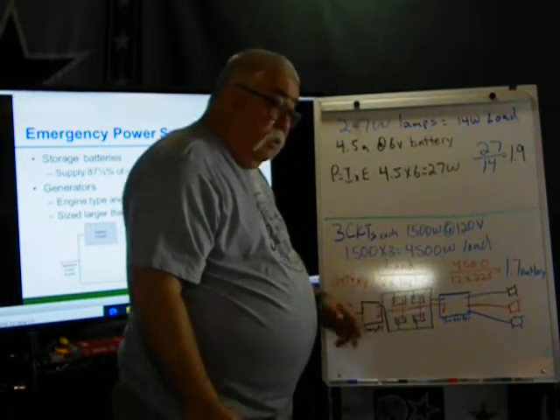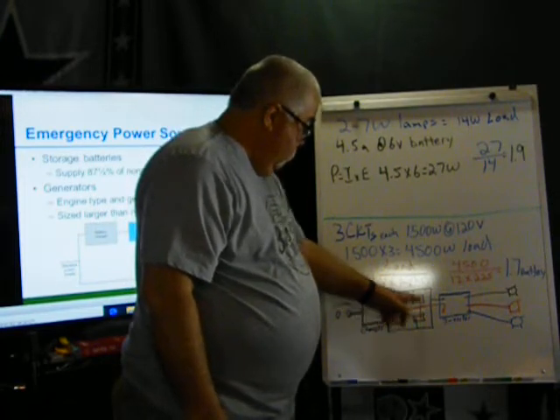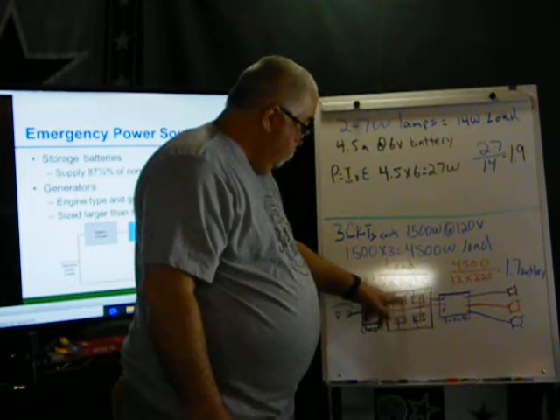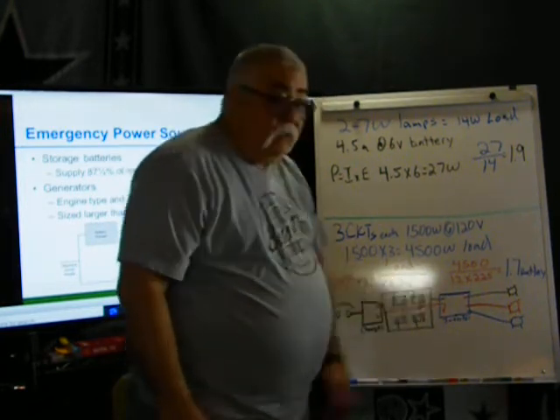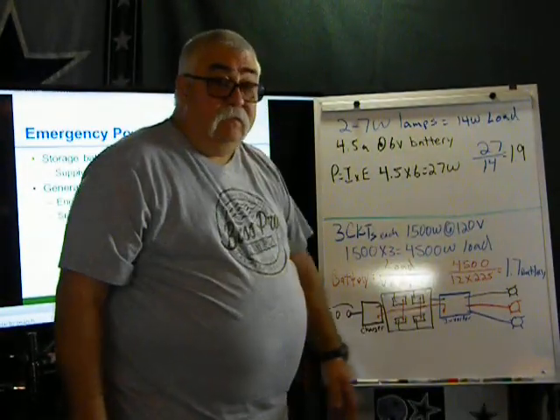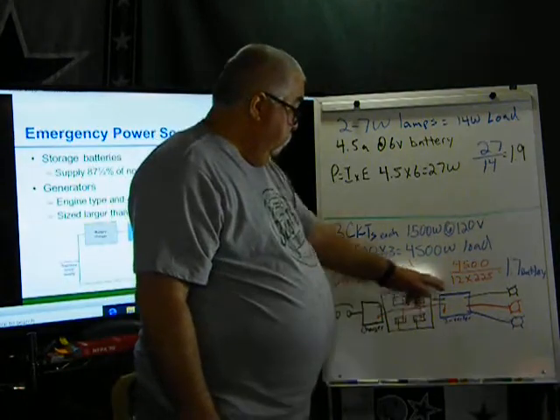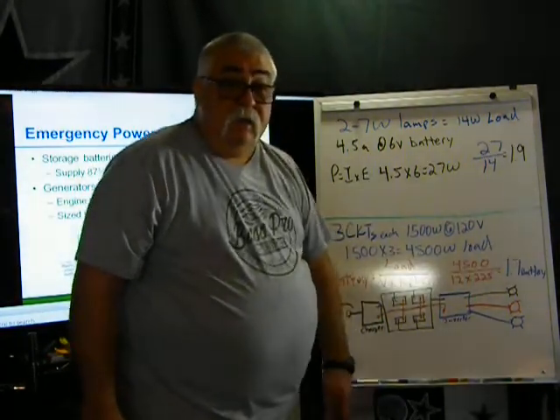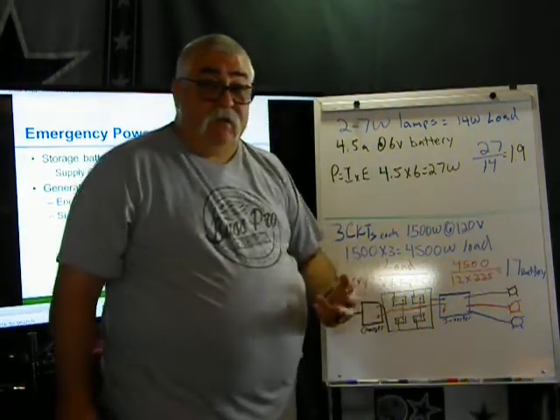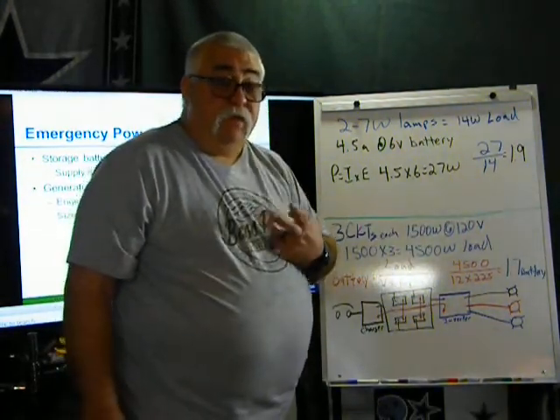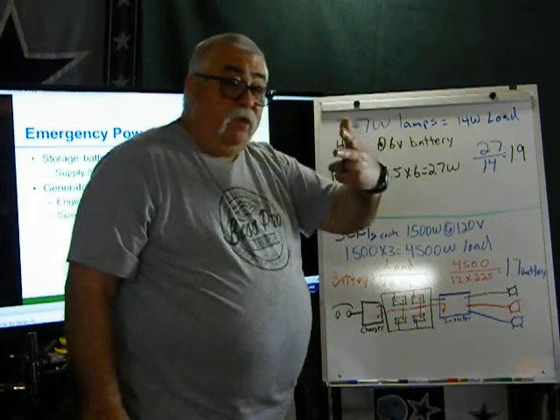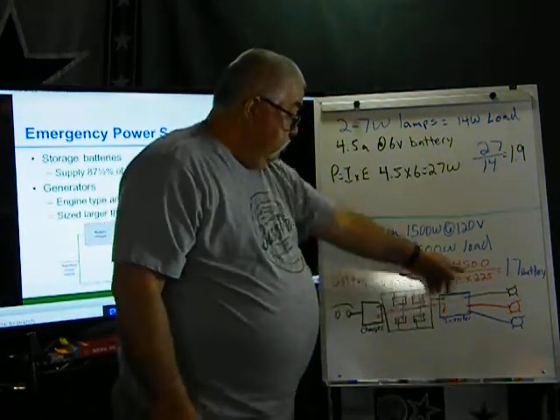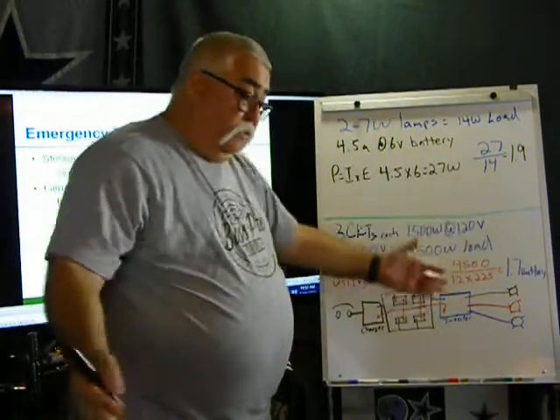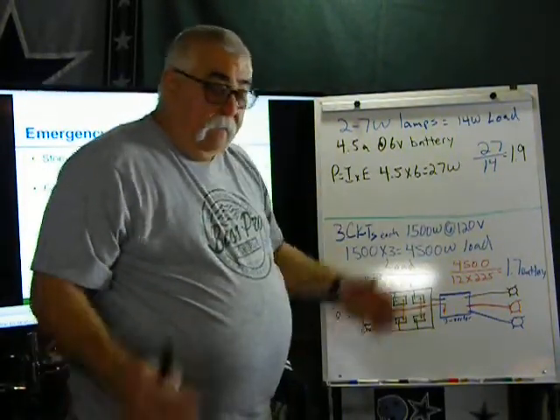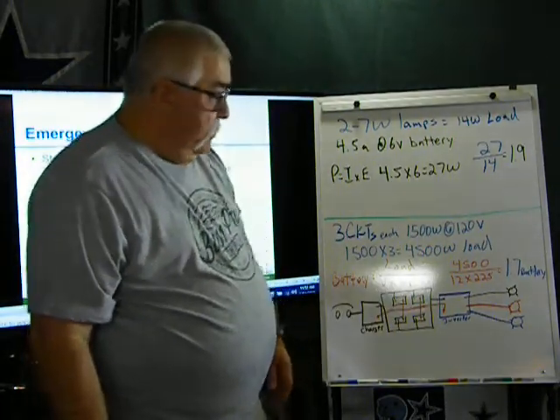Okay, so now if I was going to put them in series, I'd have a negative coming to here, my positive going to there, and then from here to here I would have gone across. And that would give me 24 volts. 12 plus 12, 24 volts. Okay, it wouldn't change. Because if this is 24, it'd still be 1.7. But if I'm using 12 volt batteries in series, I still need the 1.7. That means I will need 2 series runs at 2 batteries each, 225. Okay, or I can always buy a 225 amp 24 volt battery. They do make them.